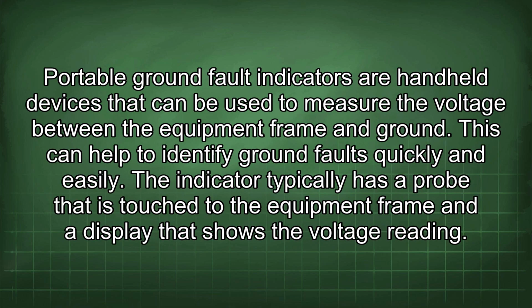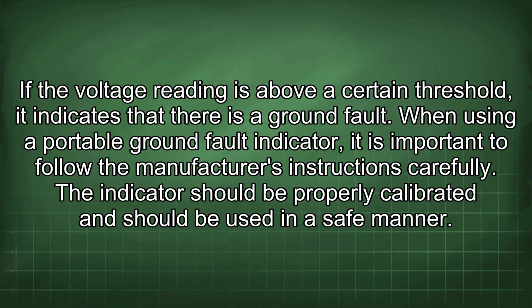Portable ground fault indicators are handheld devices that can be used to measure the voltage between the equipment frame and ground. This can help to identify ground faults quickly and easily. The indicator typically has a probe that is attached to the equipment frame and a display that shows the voltage reading. If the voltage reading is above a certain threshold, it indicates that there is a ground fault.